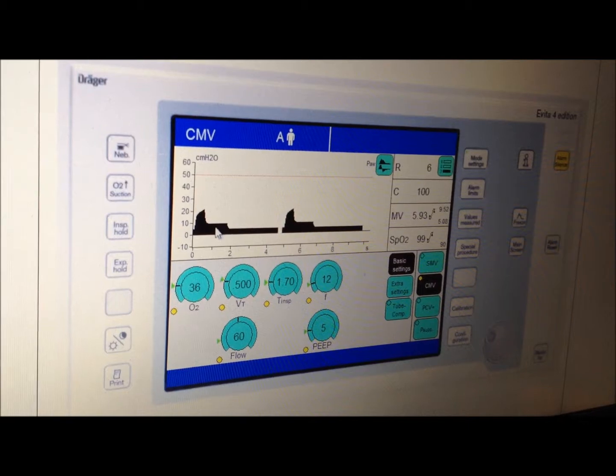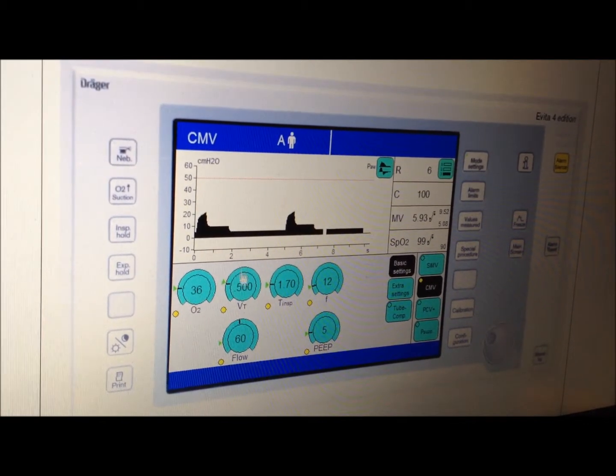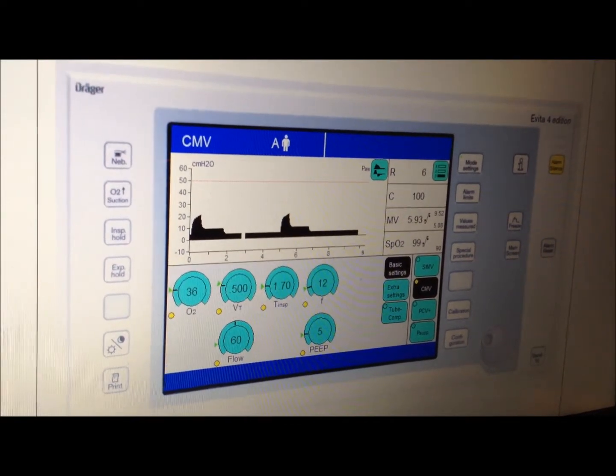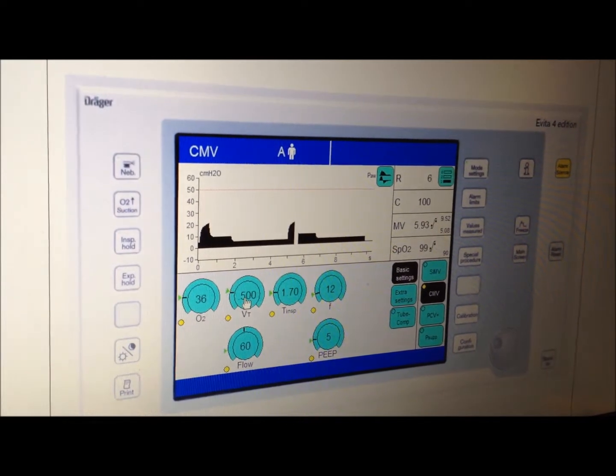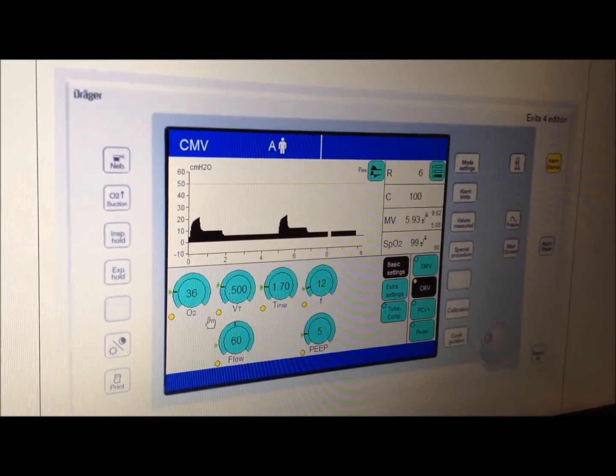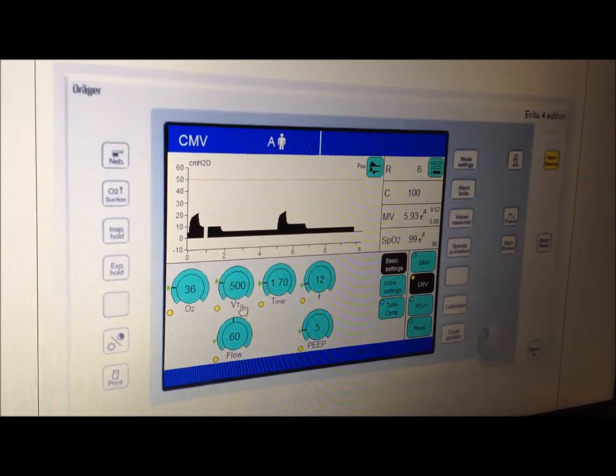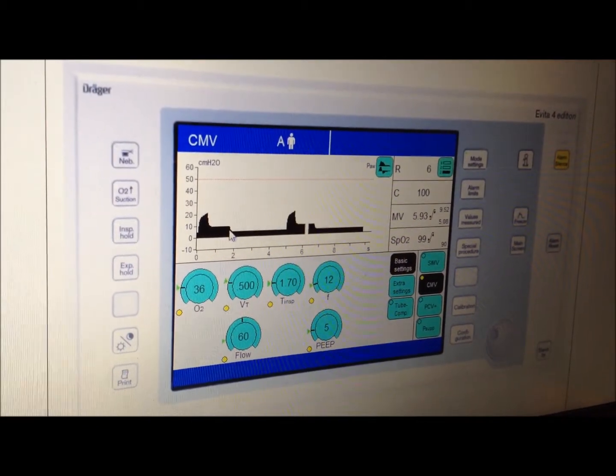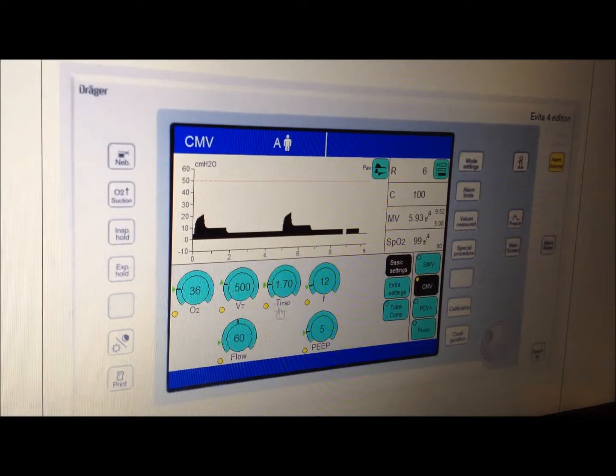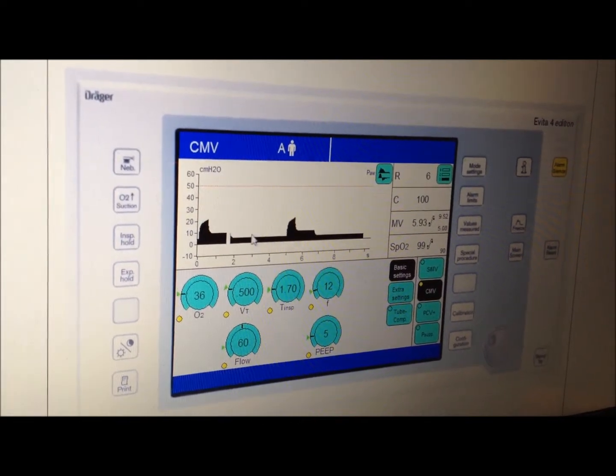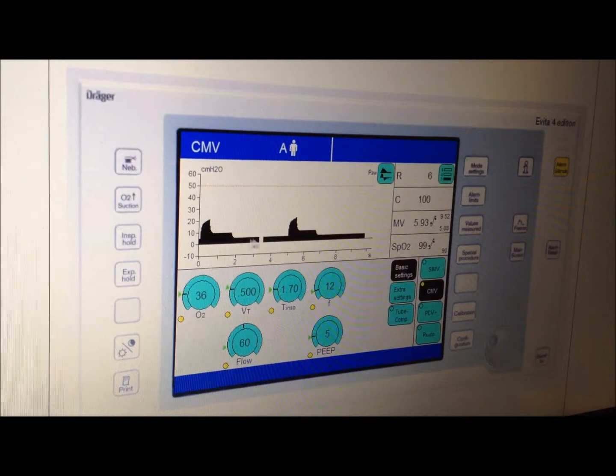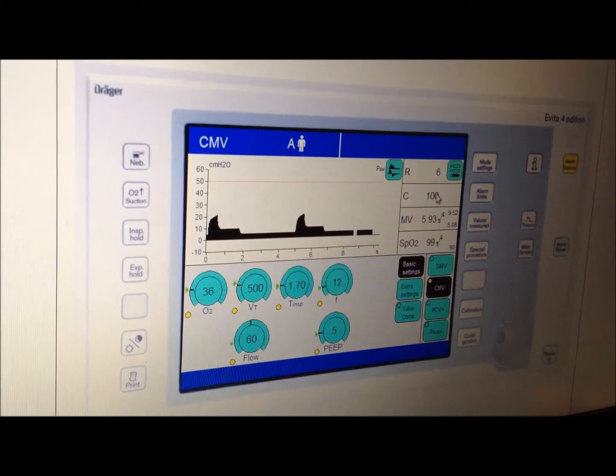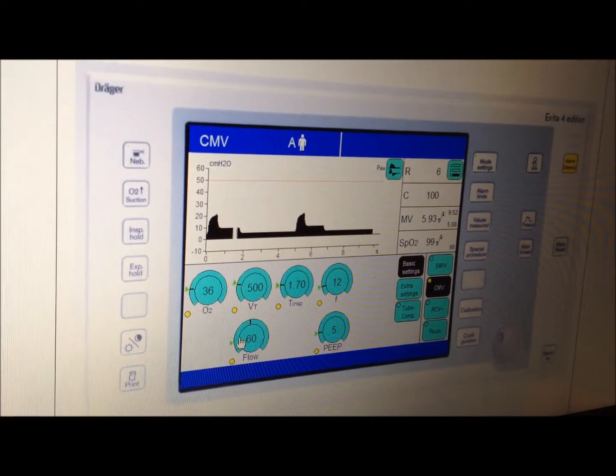The plateau pressure remains unchanged because it depends only on tidal volume and compliance. Plateau pressure = tidal volume / compliance = 500 mL / 100 = 5 cmH2O. Adding the PEEP of 5 cmH2O gives a total plateau pressure of 10 cmH2O. So plateau pressure is not affected by changing the flow — only by tidal volume and compliance.